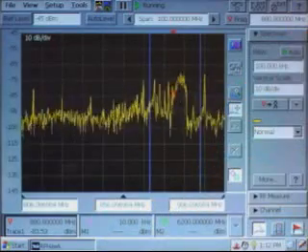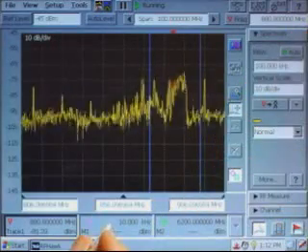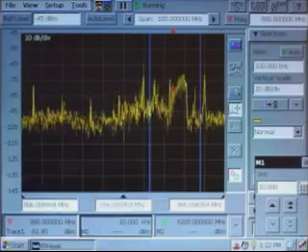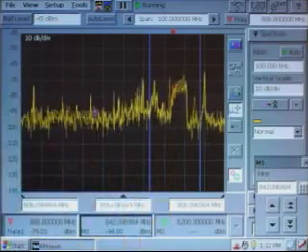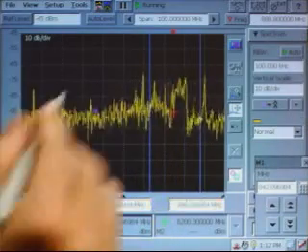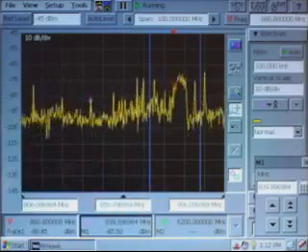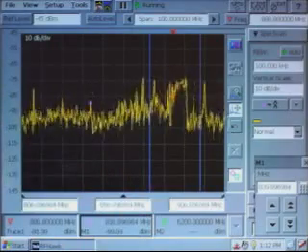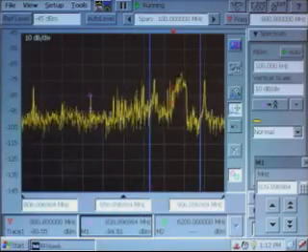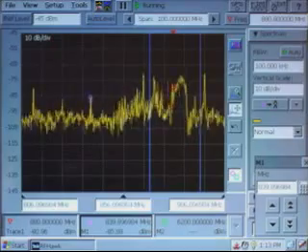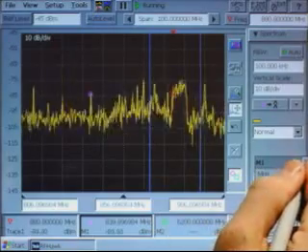In the spectrum window, there are the traditional methods of positioning markers, but the H600 also has a much easier method of simply selecting a marker and tapping the screen above the signal you want marked. This effectively makes obsolete the controls like marker to max or marker to peak or marker to next left or right on other conventional spectrum analyzers.